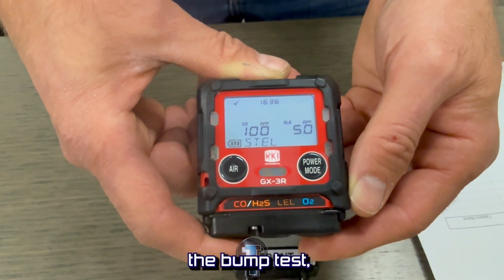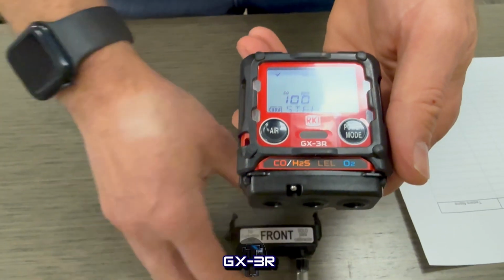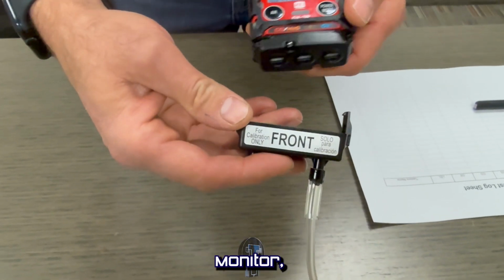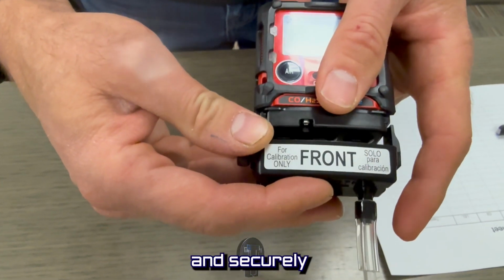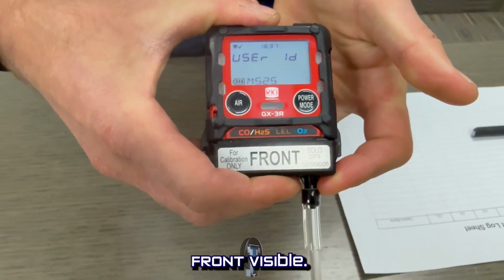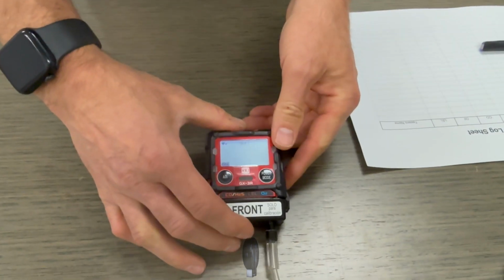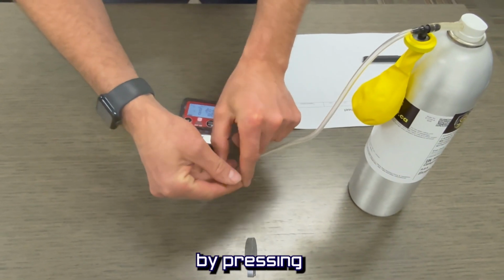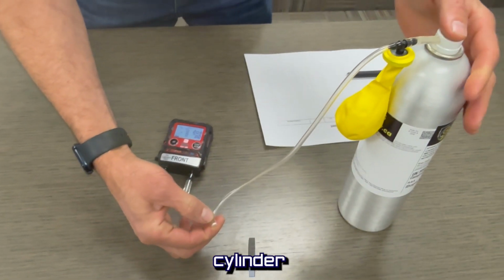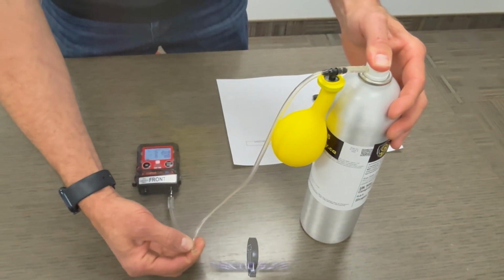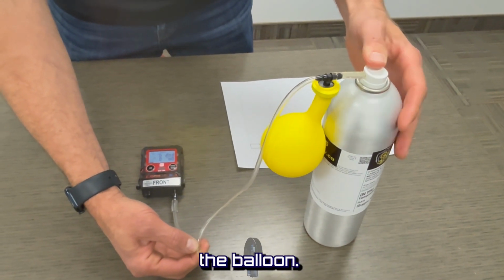To start the bump test, attach the calibration cup to the GX3R Personal Gas Monitor, ensuring it is properly oriented and securely fitted with the label front visible. Pinch the tube between the balloon and the personal gas monitor. Slowly inflate the balloon by pressing down on the button on the bump test gas cylinder until the balloon is slightly inflated, making sure not to overinflate the balloon.